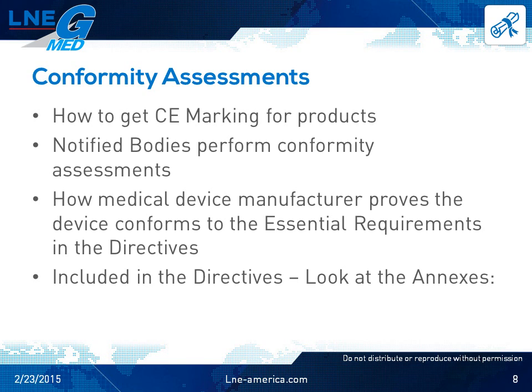Now, as you'll see, Class 1 devices that aren't sterile or don't have a measuring function don't require a notified body to perform a conformity assessment. Some other products directives also require notified bodies to perform conformity assessments. The conformity assessments are all included in the directives, regardless of the product that they're for, in the annexes. A breakdown of all of the conformity assessments is on the next couple slides.